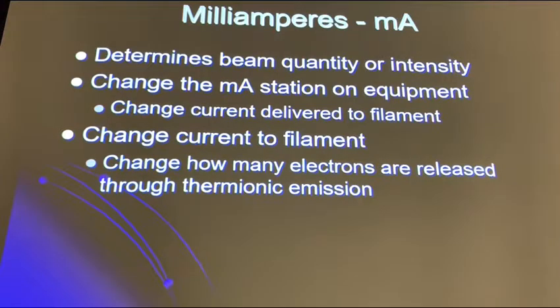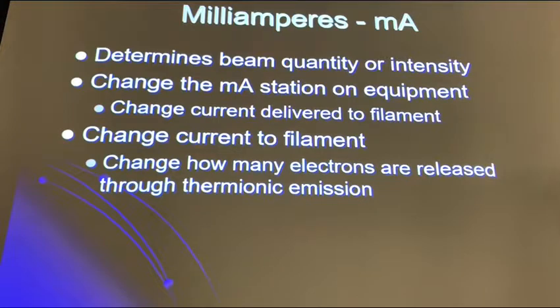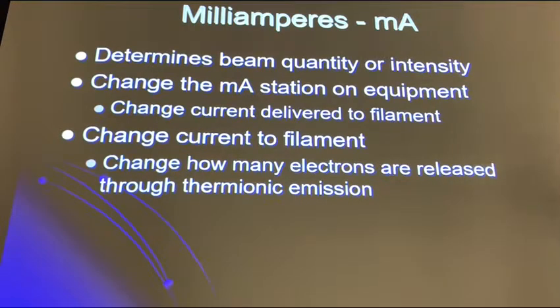Changing current to the filament changes how many electrons are released through thermionic emission. In the x-ray circuit, you have a step-up transformer and a step-down transformer. More electrons are available when you go to a higher MA station, or you can use less time to end up with the same MAS total.